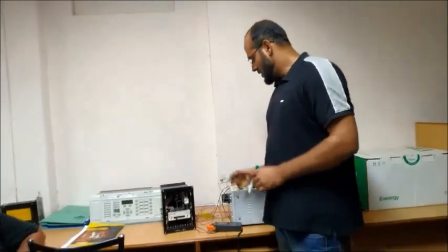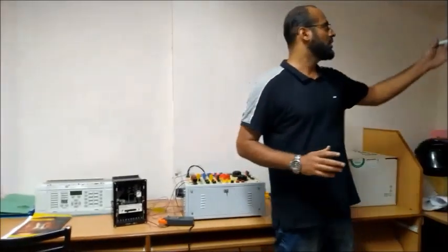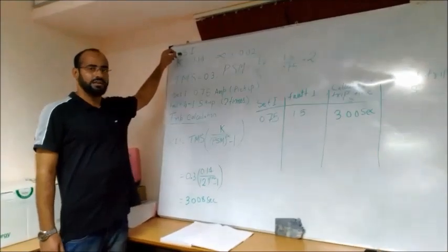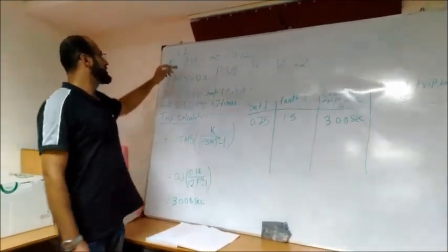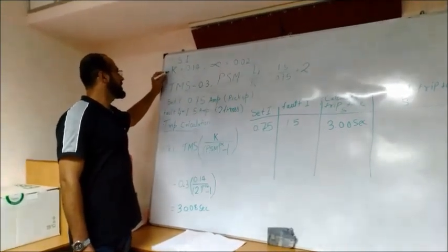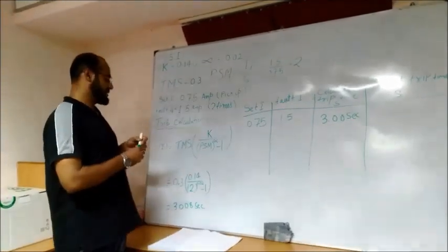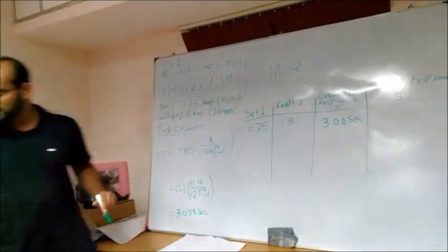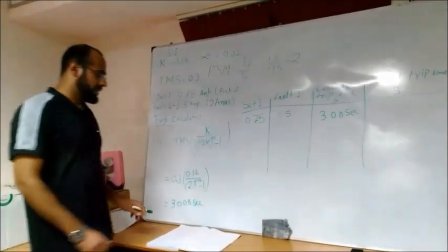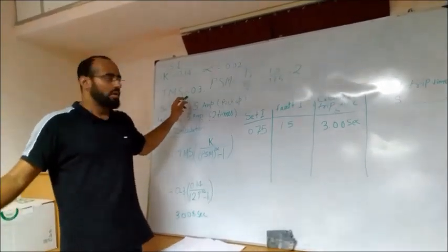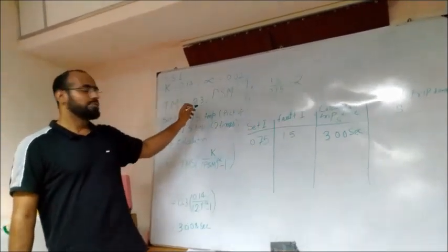So first we should know the theory part of how it works. So here we go. So basically this relay is our standard inverse relay. We need two values, that is our constant value, that is K and that is alpha. So we should set first the TMS. The TMS value that is we already set in our breaker 0.3.